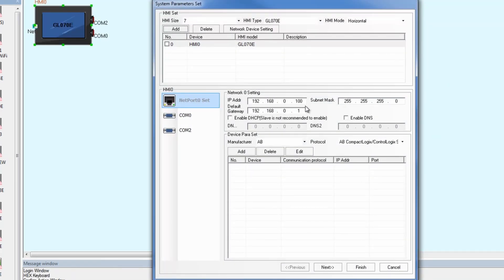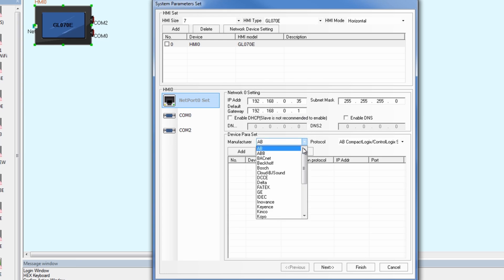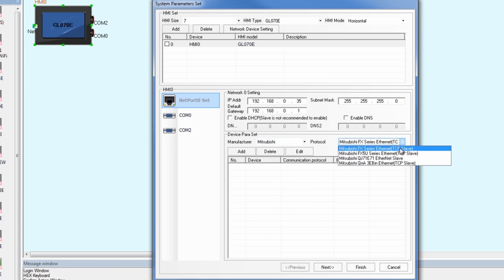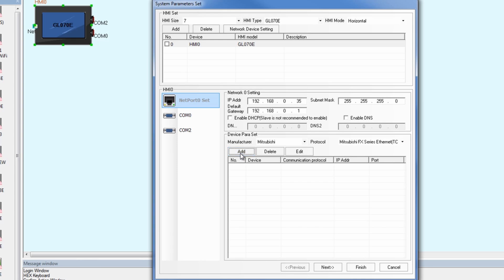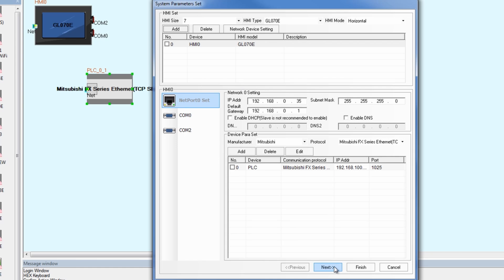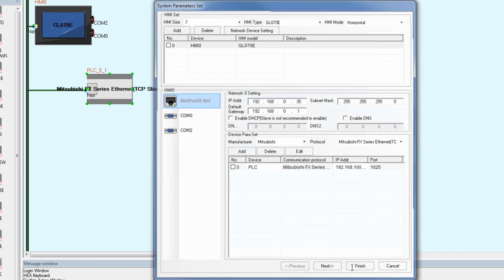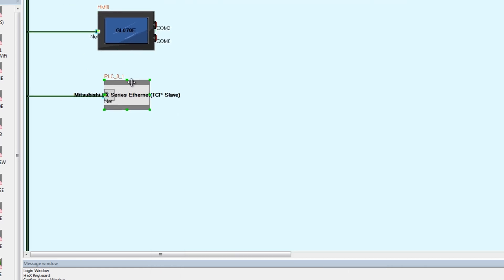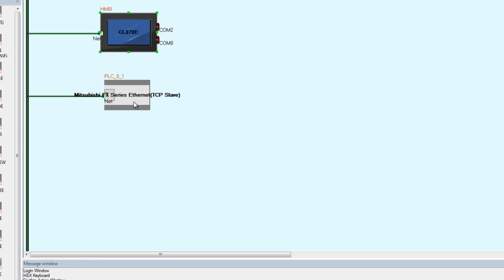We're going to go to our network port settings. Let's set these the same way. So we had 192.168.0.35 and 38. Let's go ahead and go to Mitsubishi, FX series Ethernet TCP slave. Add, and we set that as 38, port number 1025, station number one. Hit okay, hit finish. So these are set up the same way that we saw in that guide in the manual.